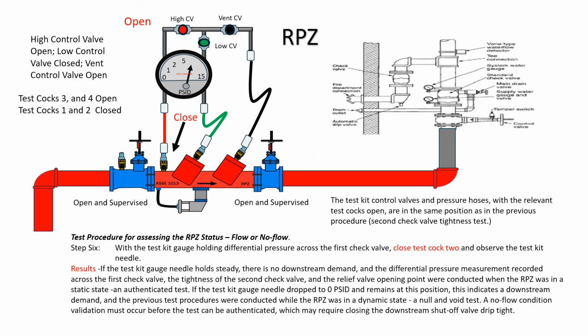Test procedure for assessing the RPZ status, flow or no flow. The test kit control valves and pressure hoses, with the relevant test cocks open, are in the same position as in the previous procedure, second check valve tightness test. Step 6. With the test kit gauge holding differential pressure across the first check valve, close test cock 2 and observe the test kit needle. Results. If the test kit gauge needle holds steady, there is no downstream demand, and the differential pressure measurement recorded across the first check valve, the tightness of the second check valve, and the relief valve opening point were conducted when the RPZ was in a static state.